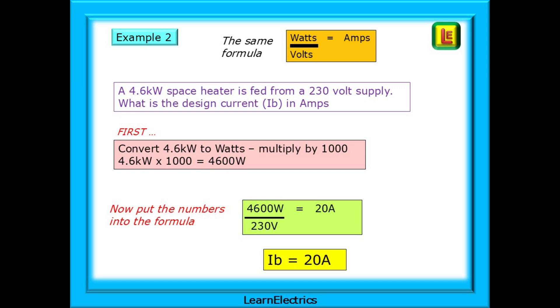Another example. This time, a 4.6 kilowatt space heater is fed from a 230 volt supply. What is the design current, IB, in amps? The first thing we must do is to convert kilowatts into watts. To do this, multiply the kilowatts by 1000 so that 4.6 kilowatts is the same as 4,600 watts. Now we can put the numbers into the formula. 4,600 watts divided by 230 volts is 20 amps. And this is our answer. IB, the design current, is 20 amps. And we will use this 4.6 kilowatt heater for the rest of the video.